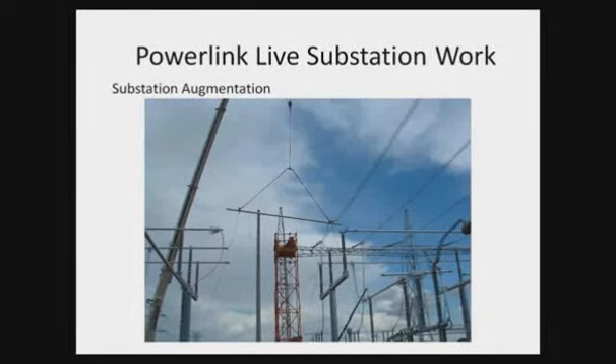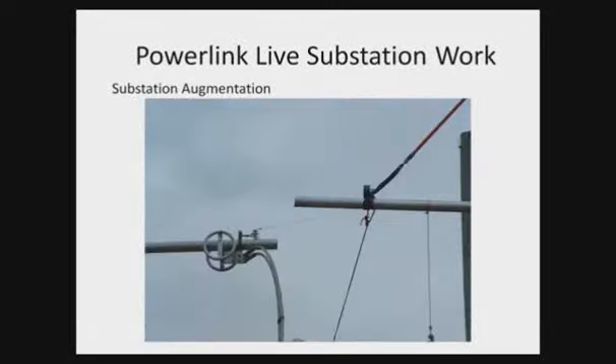We spoke before about connecting bus bars. So this is one of the bus bar jobs where we've actually inserted the bar in. So the new bus bar is on the right-hand side of the photo. The existing old bus bar is on the left-hand side of the photo. You can see on that particular phase, first we had to go up and cut the old spheres that used to be on the end of the bar off. We're using a crane in this particular case, so we're just lifting down into position the bar, hanging off that hook a series of insulated hot sticks that insulate between the crane and the actual bar that's been inserted into position.